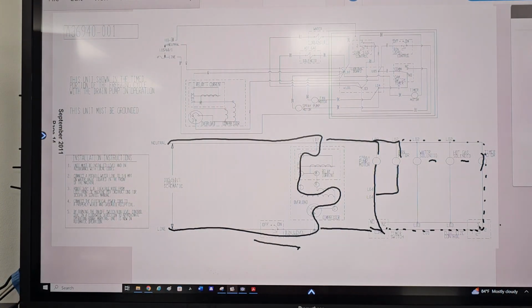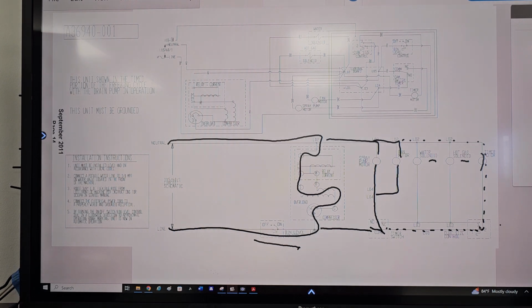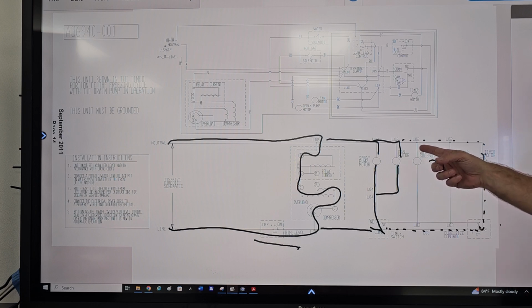So a customer calls you out and says, I don't have no ice. During ice production, we're only looking for three parts working: the compressor, the spray pump spraying the water up into the evaporator, and the fan motor. That's it. What fan motor are we talking about? The evaporator, what was across the evaporator? We don't have an evaporator fan. What fan did I just show you?